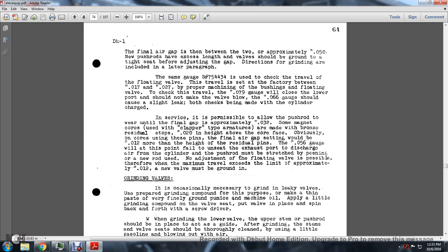In service, it is permissible to allow the pushrods to wear until the final gap is approximately 0.032 inches. The magnet cores with the clapper-type armatures are made with bronze residual stops 0.020 inches in height above the core face, so the final air gap between the settings would be 0.012 inches more than the height of the residual pins. The 0.056-inch gauge will fail to unseat the exhaust port to discharge air from the cylinder, but the pushrod must be stretched by peening, or a new rod used, if it does not reach the required adjustment.